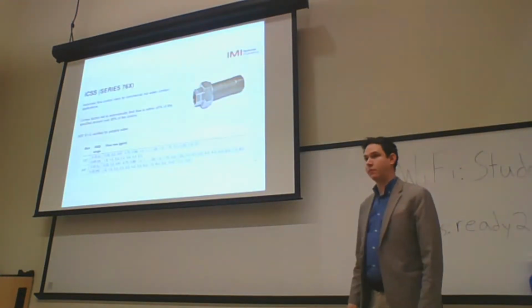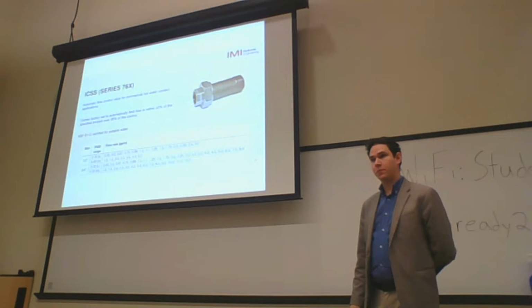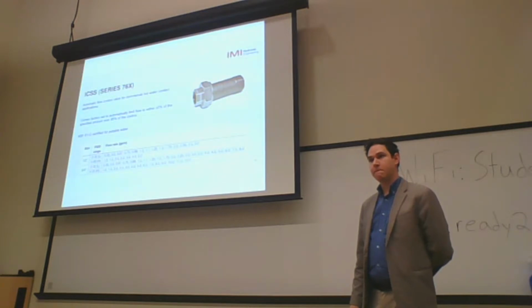The reason why I asked is because we talked about it this morning, and at lunchtime I got a call from a plumber. He was asking me questions about a recirc line, which apparently has to be within 2 feet of a hand wash device. And this is a nursing home, so it means every room going down, and he's got 3/4 inch circuits, a 3/4 inch line on the return. If you put 0.33 gallons in each, by each sink, you're going to have a pretty large pump.